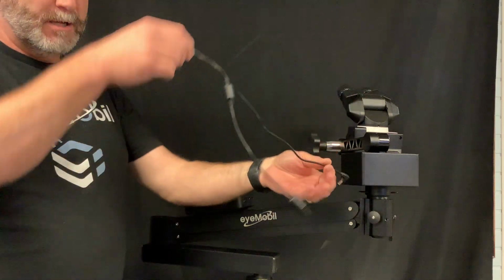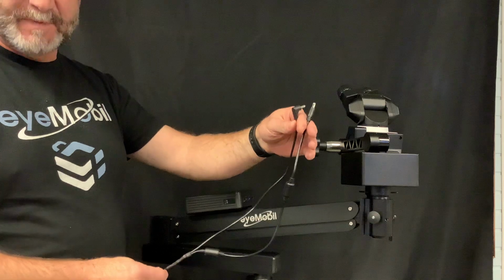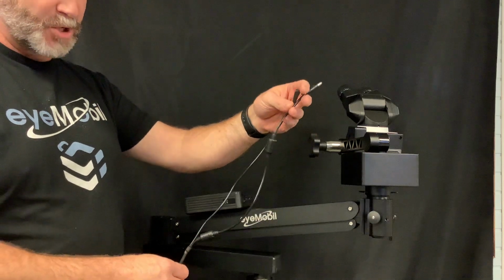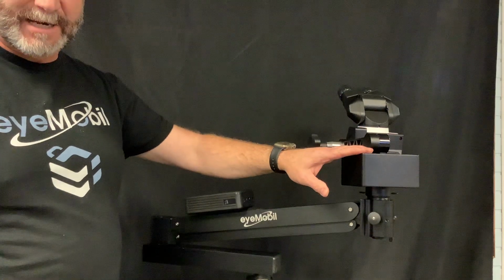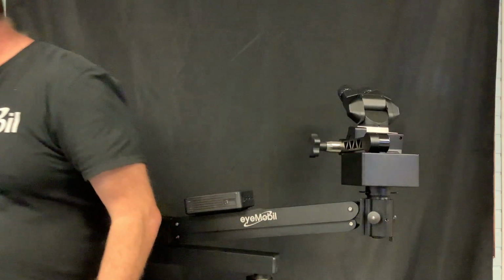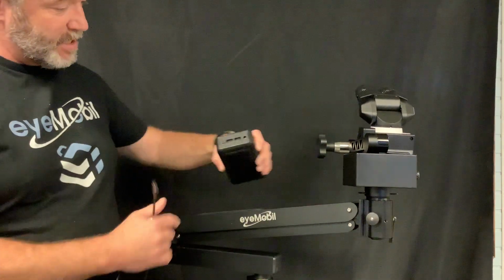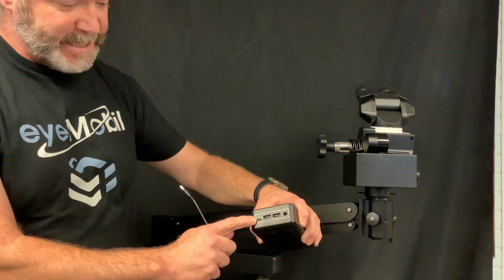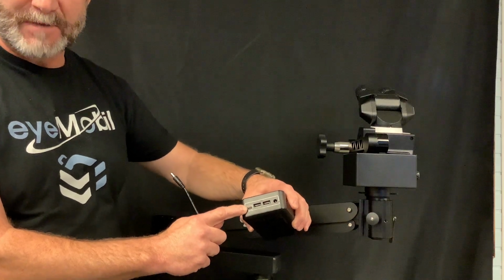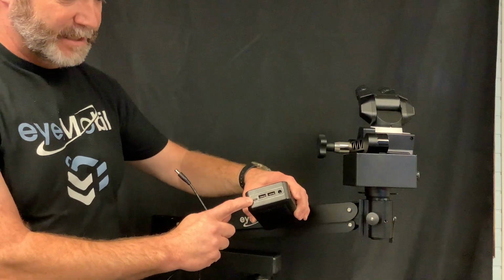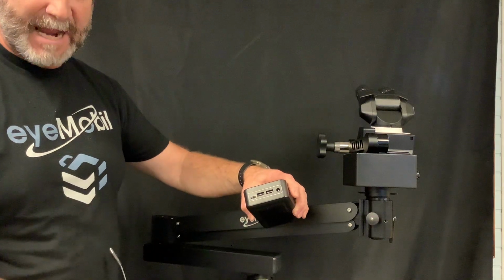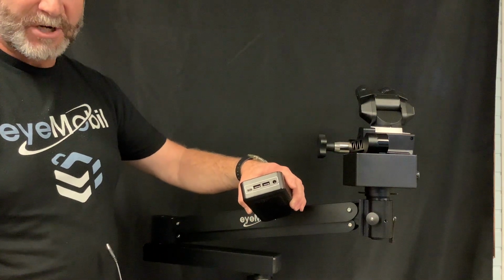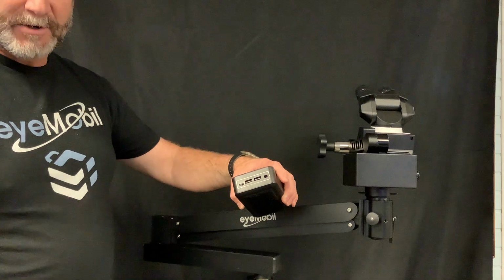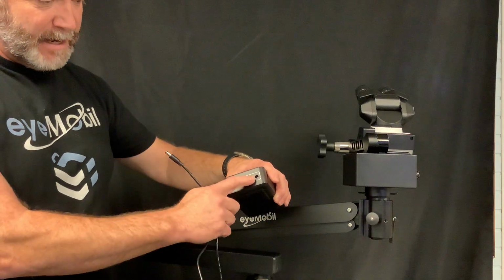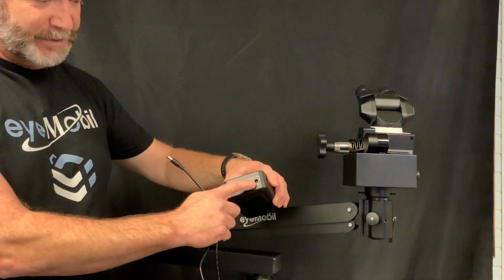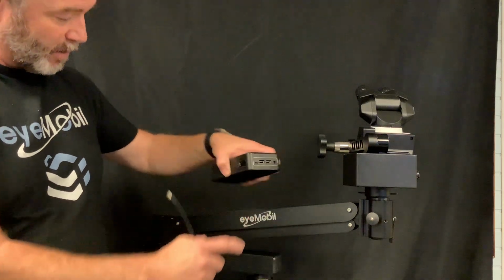This special spliced cable is what must be used anytime the scope is being used in the XY configuration. The standard USB-C cable that connects to this port of the battery is what we recommend anytime you're not using the XYZ configuration. The two USB-A ports are available for charging the iPads or any other accessories you may have. But for the XY configuration, we'll need to use the round DC port.